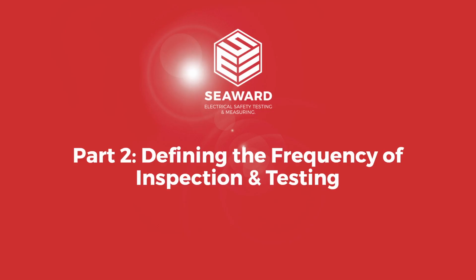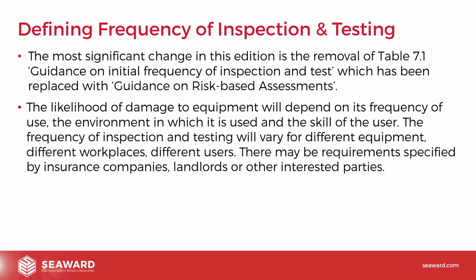In part 2, we'll look at defining the frequency of inspection and testing. The most significant change in this edition is the removal of Table 7.1, Guidance on Initial Frequency of Inspection and Test, which has been replaced with guidance on risk-based assessments. The likelihood of damage to equipment will depend on its frequency of use, the environment in which it's used, and the skill of the user. The frequency of inspection and testing will vary for different equipment, different workplaces, different users. There may be requirements specified by insurance companies, landlords, or other interested parties. So all of this needs to be taken into account when we're setting frequencies, when we're actually carrying out the risk assessment.